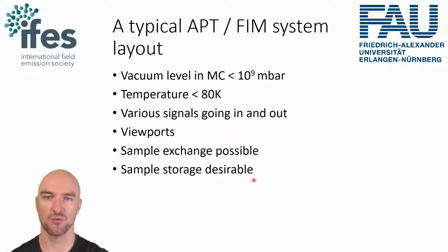Also, in many cases, we want to have the ability to store some samples inside. That's just if you have a lab where a lot of people are using an instrument, you want to have a sort of constant flow of samples in and out so that you don't lose too much measurement time, and you might want to have some sample storage, a buffer chamber. For the sample exchange, we've got a load lock, and you might want to have a buffer chamber. That's not really required, but I would say most instruments have that. But some instruments, especially for fundamental research, where sample throughput is not that much of an issue, might not have a buffer chamber.